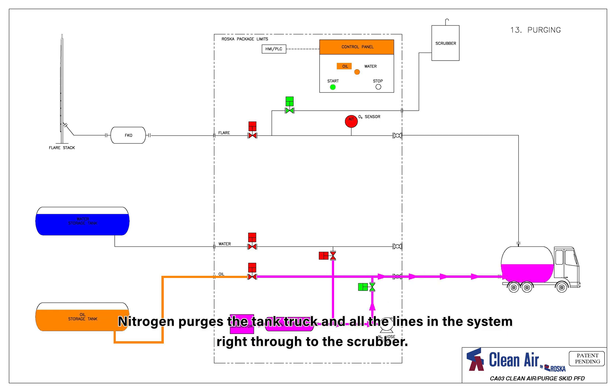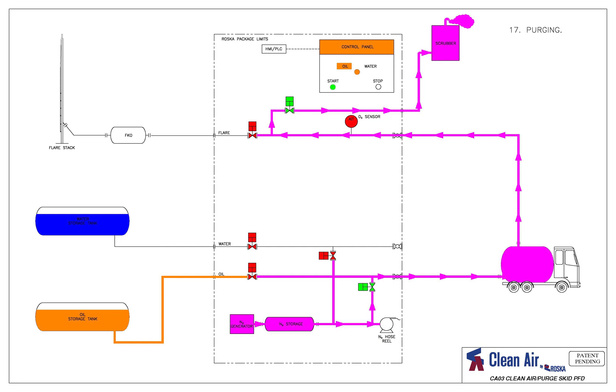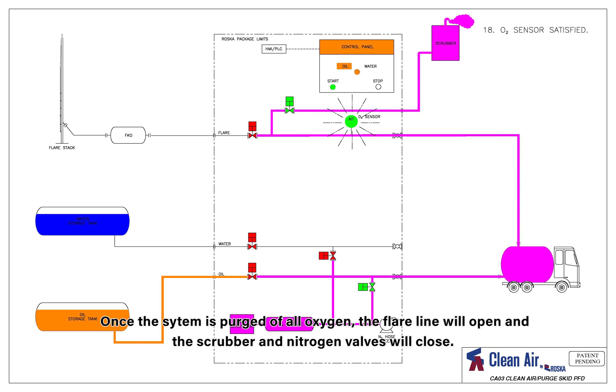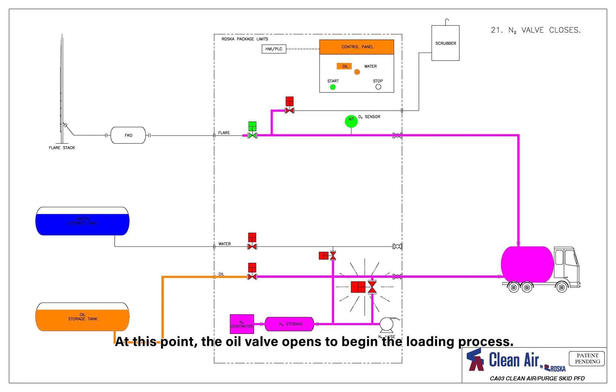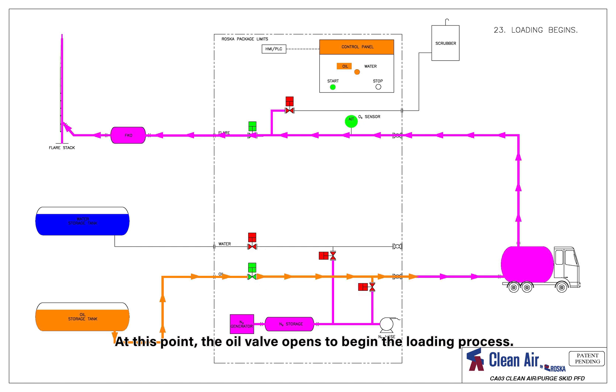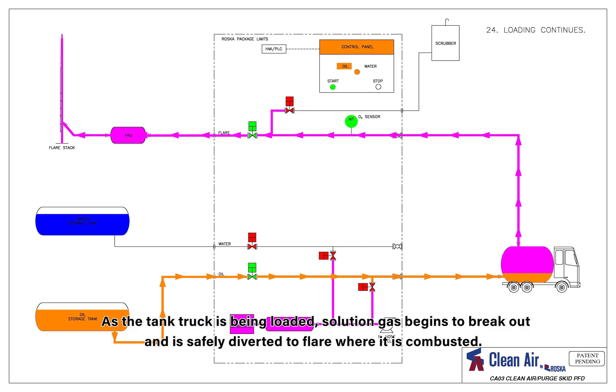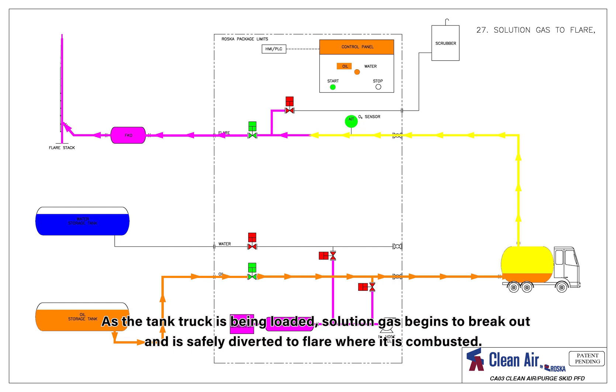Nitrogen purges the tank truck and all the lines in the system right through to the scrubber. Once the system is purged of all oxygen, the flare line will open and the scrubber and nitrogen valves will close. At this point, the oil valve opens to begin the loading process. As the tank truck is being loaded, solution gas begins to break out and is safely diverted to flare where it is combusted.